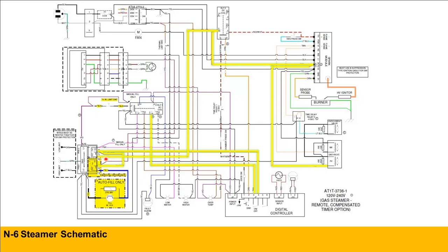If we do not have 24 volts AC coming from the open pin to ground, then we have a defective water board, meaning that the internal relay is not closing, it's not energizing. So power is just sitting there waiting, and it's really doing nothing. But once again, we do actually have 24 volts AC coming from that pin.